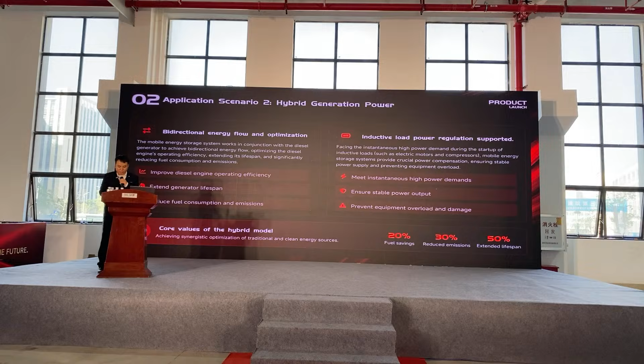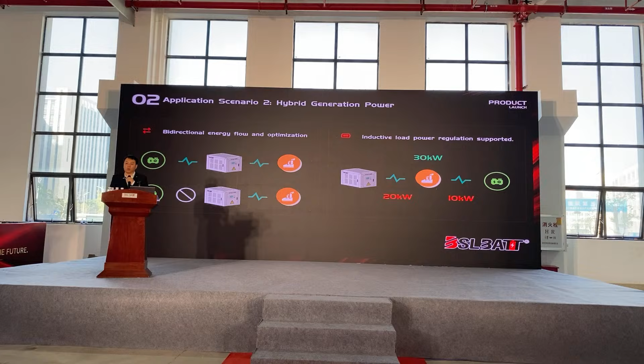The second scenario is something we've truly innovated: working alongside a diesel generator, which I think is very common in your real life. When working with a DG, our system optimizes the generator's operation in its most efficient range, roughly 40% to 80% load. By doing this, our mobile ESS can cut fuel use by 20%, reduce emissions by 30%, and extend generator life by 50%. It also provides instant power support for high inrush loads, like motors and compressors, which is very common in mining or construction areas.